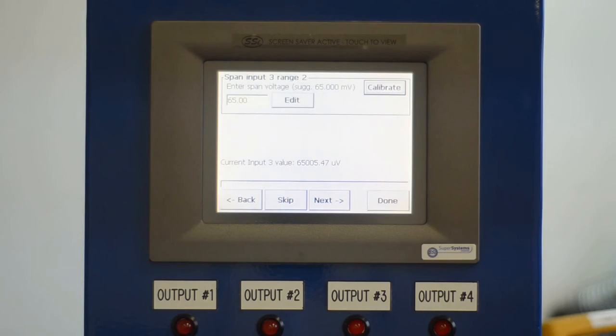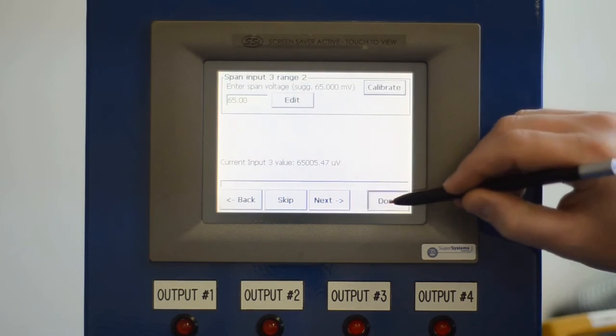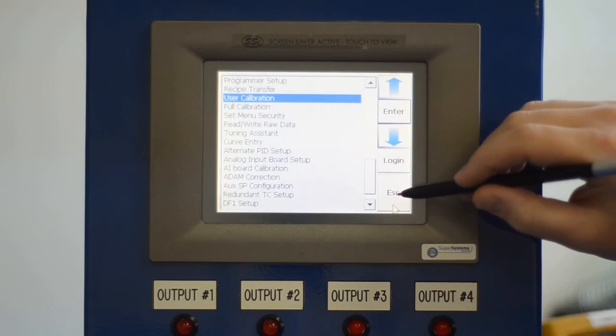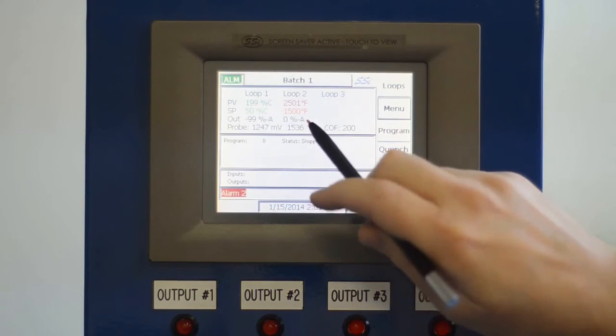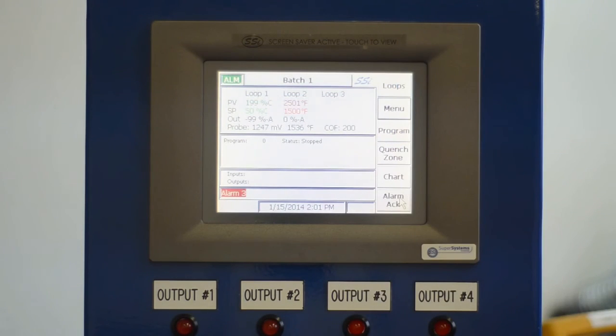Once this is complete, we can now select Done and Escape out of the menu to get back to our main screen. And this is where we're going to have to disconnect our copper wire and reconnect our TC wire, and then we will source in from our meter thermocouple measurements to check our cold junction.